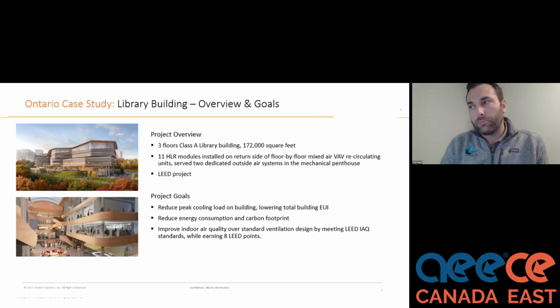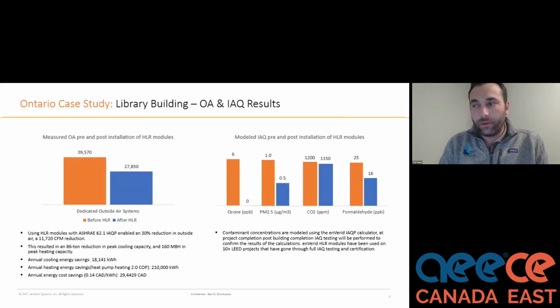So 8 LEED points were applied here while reducing the total amount of outside air significantly to reduce that peak cooling load. Here's a quick little snapshot of the total impact there. In terms of the outside air reduction, 12,000 CFM roughly were reduced by applying those 12 filter boxes. That's pretty significant. That's a 30% reduction in outside air. So a little bit less than what we typically see because LEED has a higher standard for indoor air quality than your standard ASHRAE building. But we were still able to shave off 86 tons of peak cooling capacity, more than making up for the first cost of these systems being deployed.